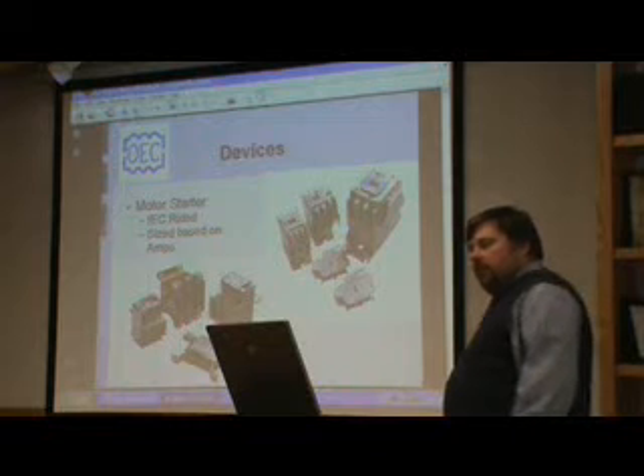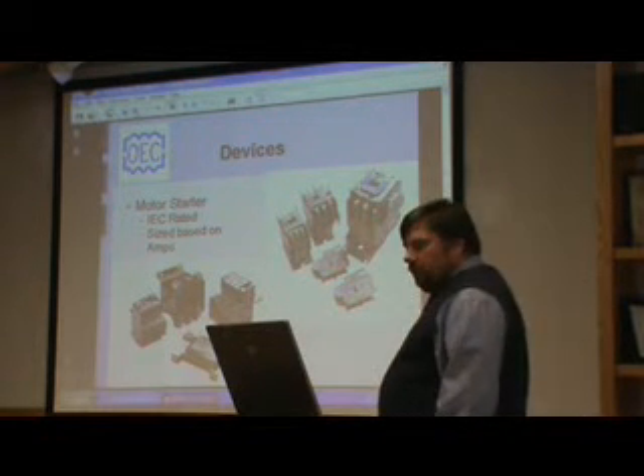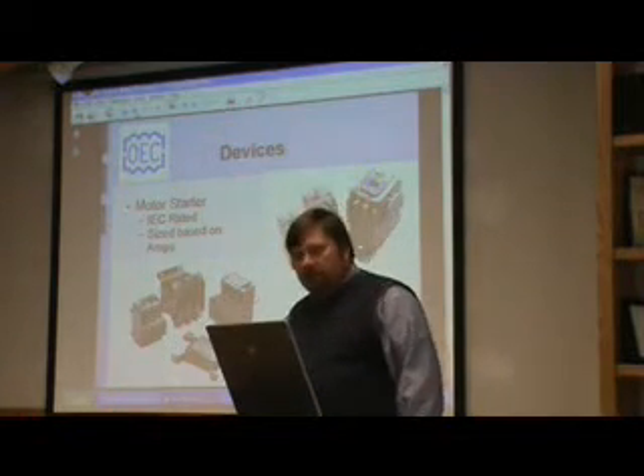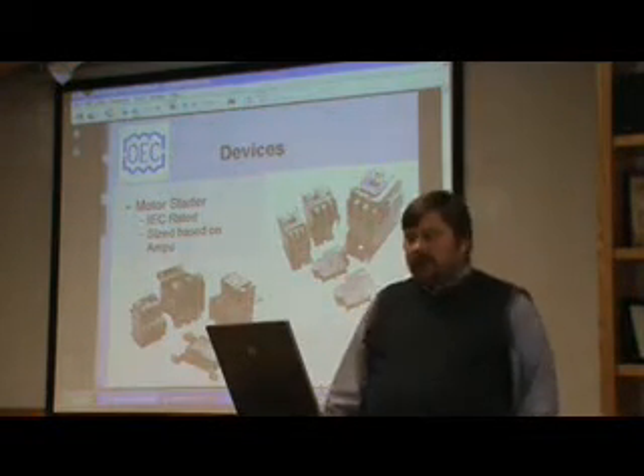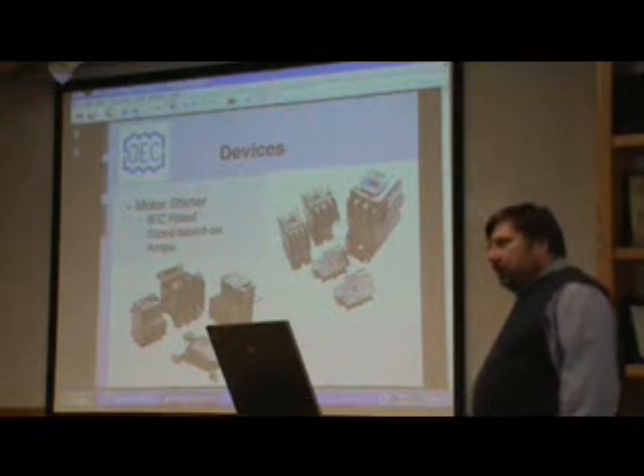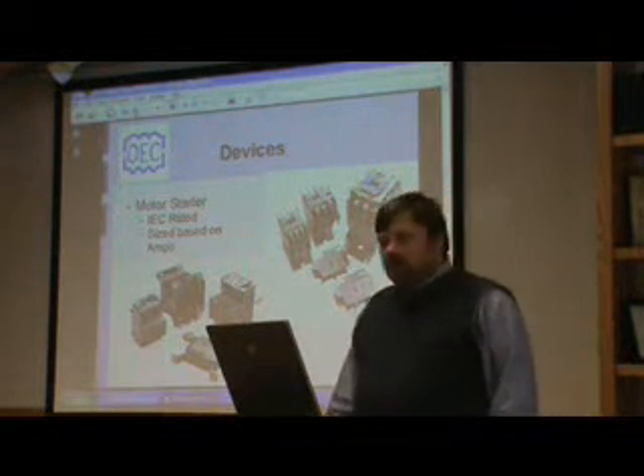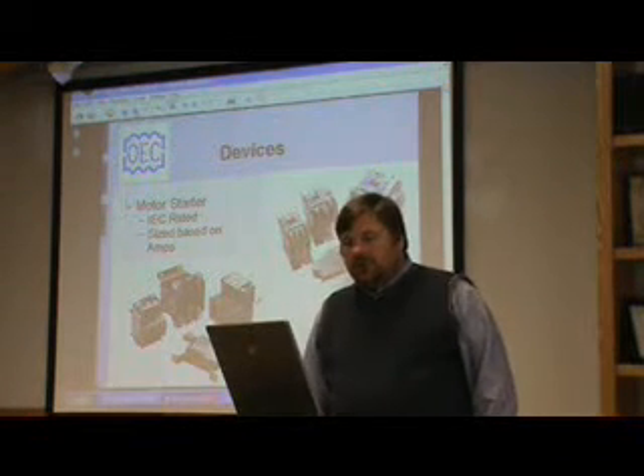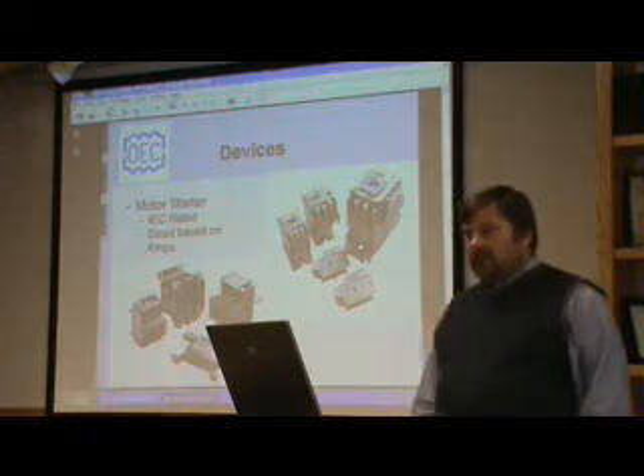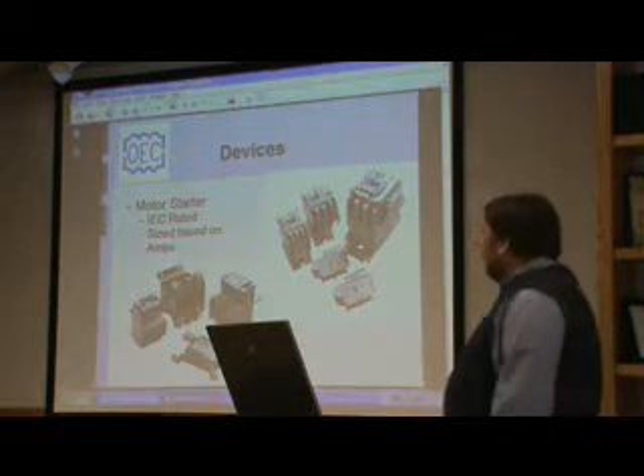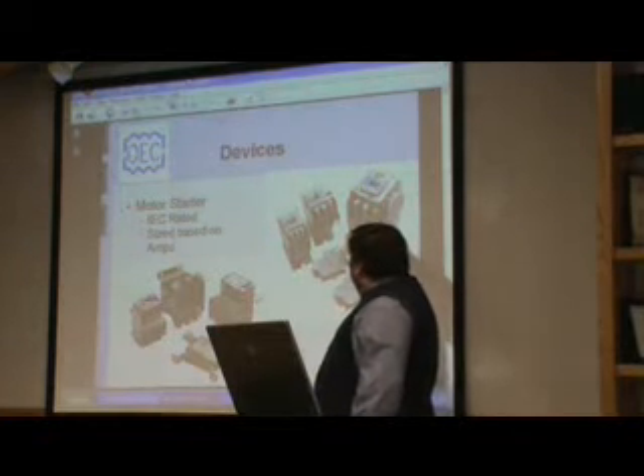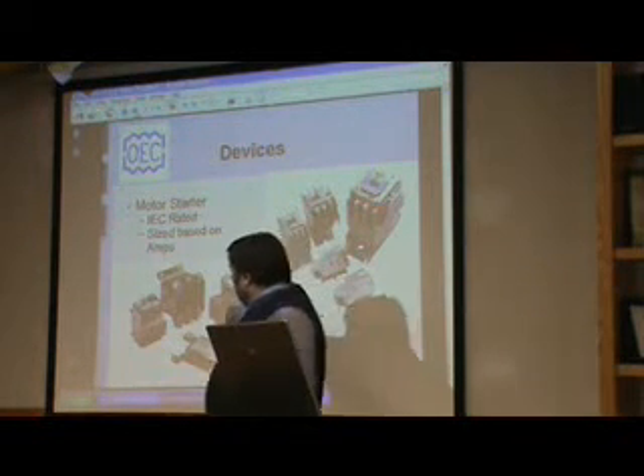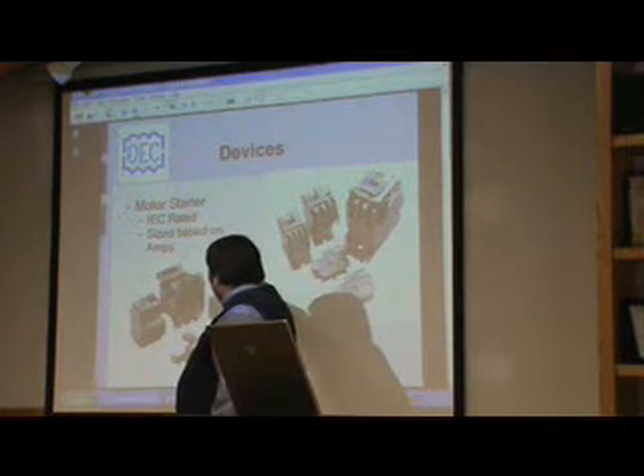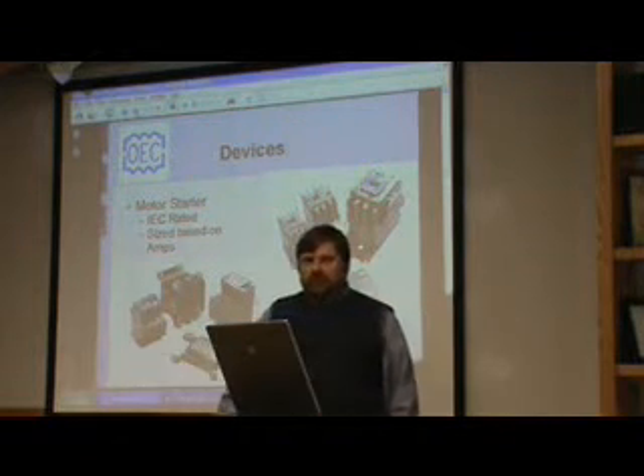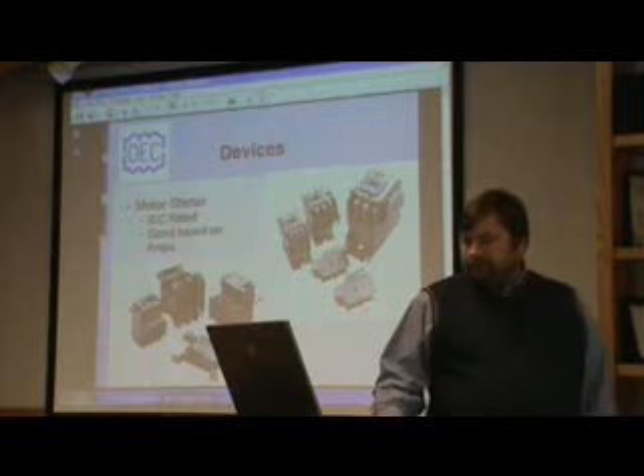When you come to motor contactors, I'm going to say there's actually three options you can use. The first of those is an IEC rated. IEC stands for International Electrotechnical Commission. It's a manufacturing group over in Europe. They got together and set up this council so that they could set a basis for standards for rating of components. Here you see the IEC contactors, and down in this picture you see the overloads. This is one of the older overloads where you replace the heater packs inside there. And this shows you an example of an adjustable one. It has a little dial on top where you can adjust the amperage for your particular motor.